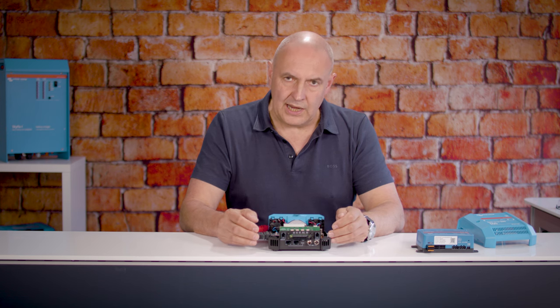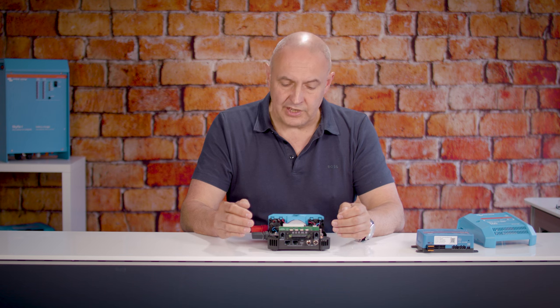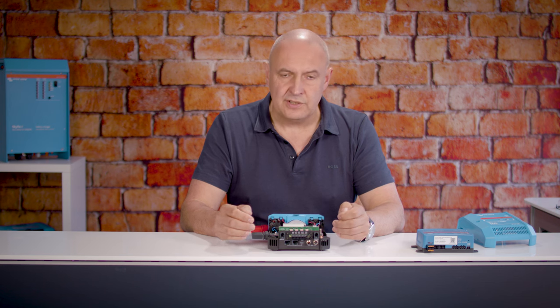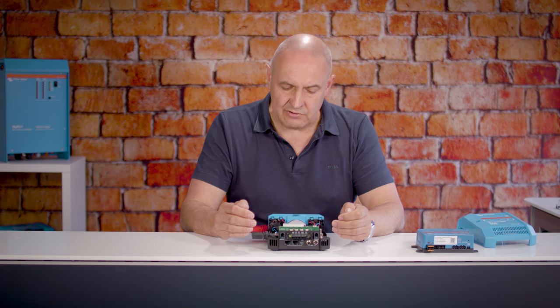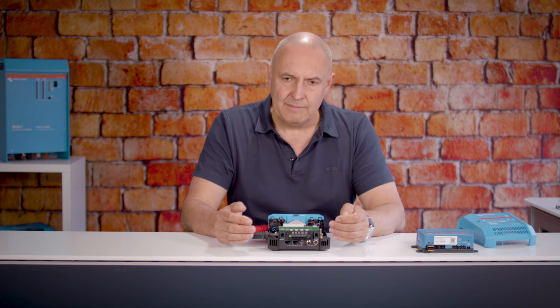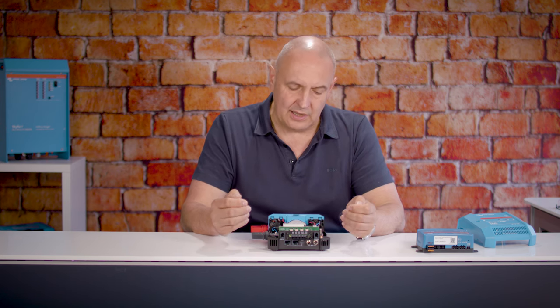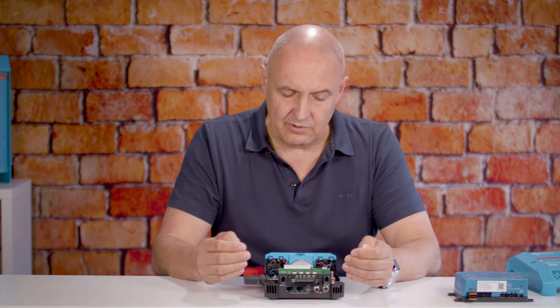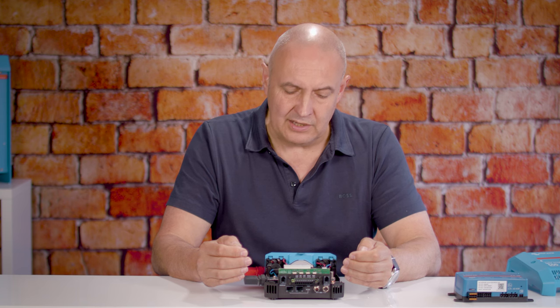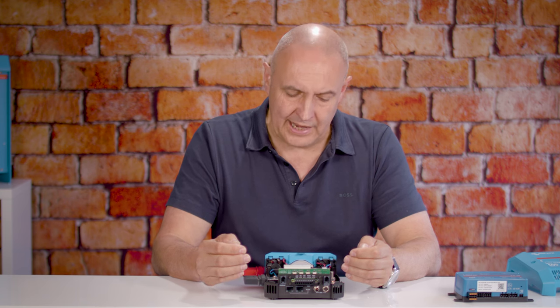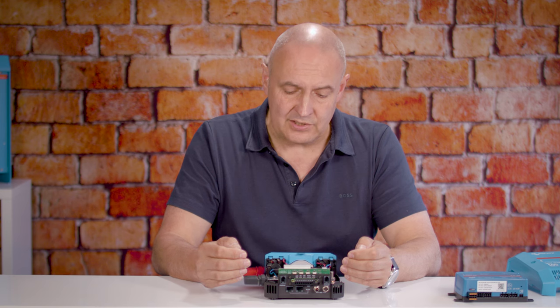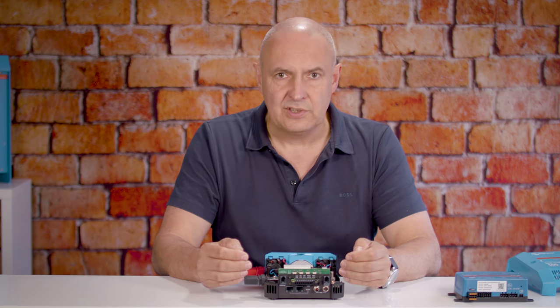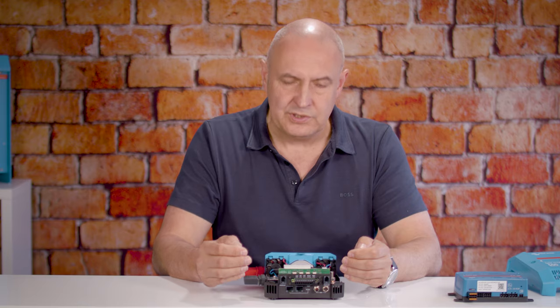One of the things when you're connecting large batteries to a large inverter charger is that there's a significant amount of inrush current when you first connect the inverter, and that's because they've got large capacitors built into them. And those capacitors take a glug of energy when you first connect them, and there's a risk during that connection period that you get an arc on that main contact, and that will degrade the quality of the contact and over time will damage the switch.